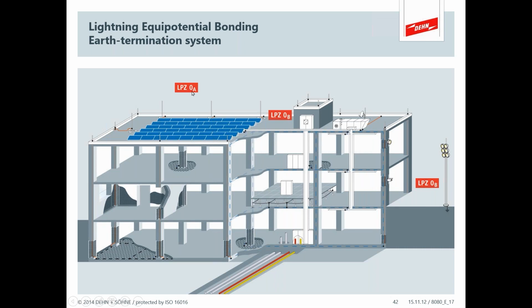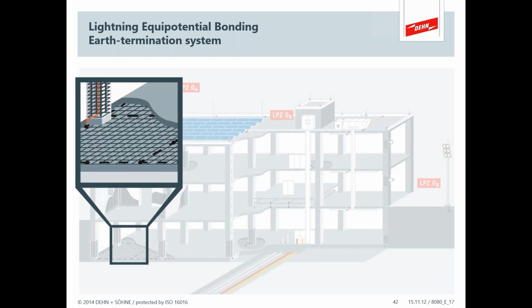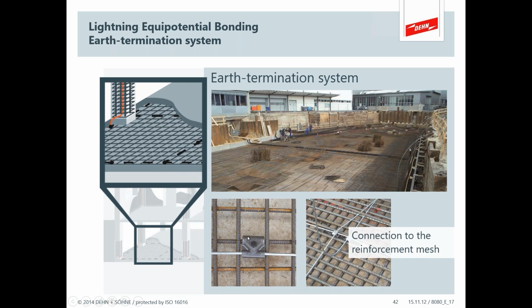So you see something that looks like that when you're looking at lightning equipotential bonding and the earth termination system, with all of this metal bonded together. You want to bond your rebars and that stuff together because that creates a very safe equipotential bonded system. It reduces things like touch and step voltage that will occur if you've got lightning in the structure. You could have high touch and step voltage around that pillar, for instance. So again, a great deal to talk about in this topic, but just remember, bond that stuff.